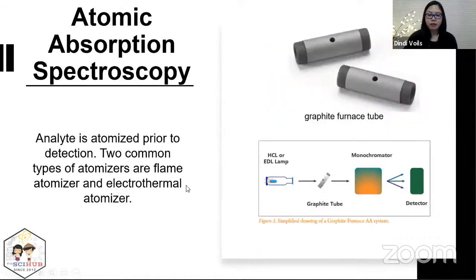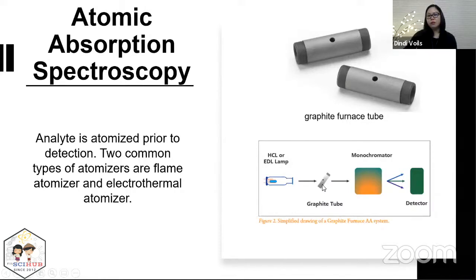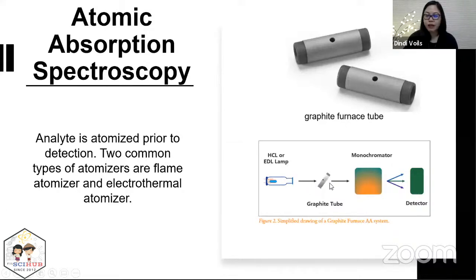The other type of atomizer is an electrothermal atomizer. An example is a graphite furnace tube, where the sample is introduced into a graphite tube that is heated by resistive heating. This converts the sample into free atoms. This method has more sensitivity because the sample is more contained in the graphite tube. An incident beam interacts with the sample, then the light gets filtered and detected for further signal processing.